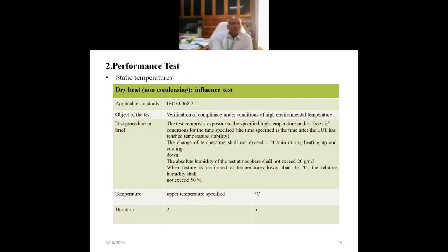Now some of the performance tests I will talk about. The dry static temperature test. The standard applicable is IEC 60068-2-2 and the object of the test is verification of compliance under the conditions of high environmental temperature. Test procedure in brief, the test comprises of exposure to the specified high temperature under free air conditions for the time specified. The time specified is the time after the EUT has reached temperature stability. The change of temperature shall not exceed 1 degree centigrade per minute during the heating up and cooling down. The absolute humidity of the test atmosphere shall not exceed 20 gram per meter cube. When the testing is performed at temperature lower than 35 degree centigrade, the relative humidity shall not exceed 50%. And temperature upper limit is specified in degree centigrade, duration is 2 hours.